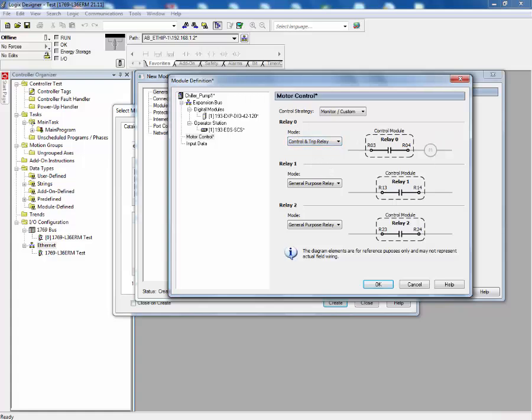This allows the end user to wire up relay 0 directly in series with the contactor coil. The user can then use a network command to control the coil and that same relay will also open when there is a trip event.